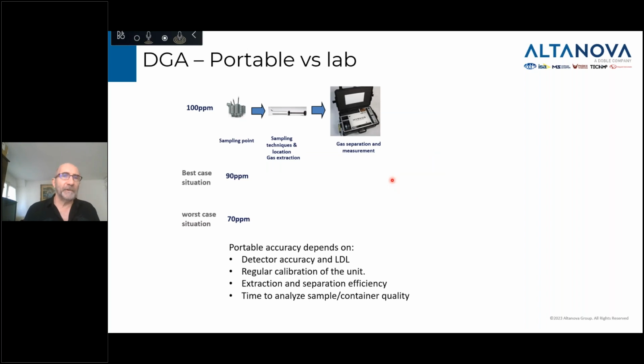Now, when you look at other ways of doing DGA, since 1965 mostly the whole world has done annual or semi-annual punctual DGA. Over the last 20 years, technology has also brought portable DGA equipment. The advantage is that you have a much shorter line of doing the DGA. You go directly to the transformer's drain valve, take your sample, and right on the spot you can do your DGA. So you cut off the time of transportation and the lead time before the measurement is done, and that has a huge impact on the amount of gas you start losing.